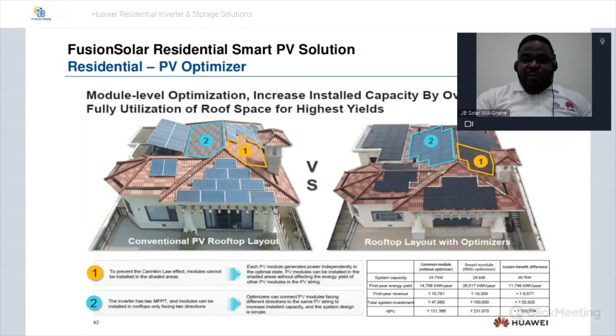Another good thing about the optimizers is that they allow you to pinpoint which module in a string has an arc fault. The inverter itself has arc fault protection, but it can only detect that a particular string has an arc fault, not which specific module is causing it. To pinpoint the particular module, you need an optimizer. Right in the palm of your hand, the optimizer will pinpoint which module in your system has the arc — easy for O&M maintenance, so when you go onto the roof you go specifically to that module to sort out the problem.